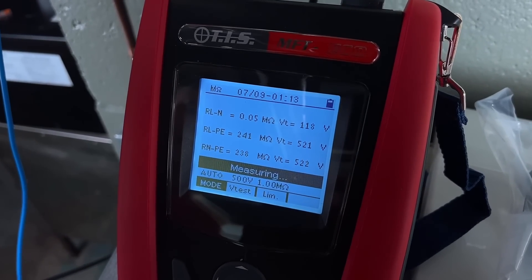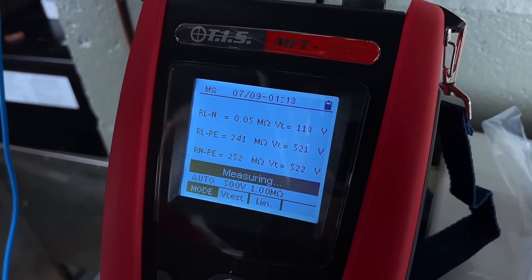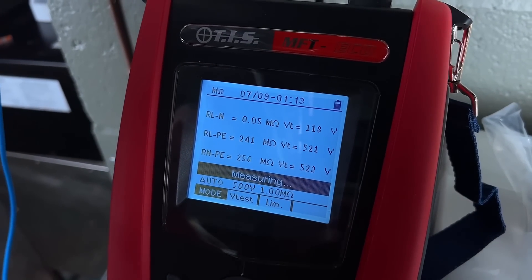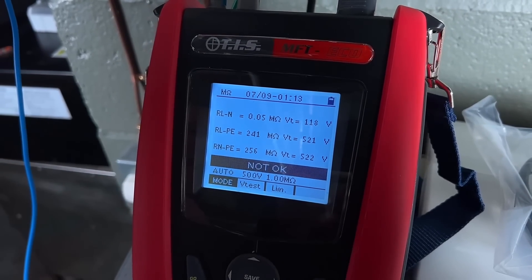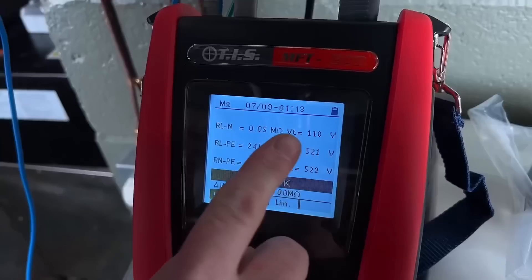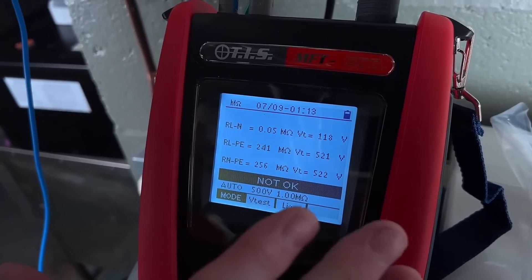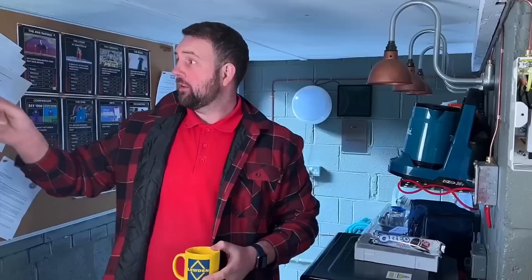It's brought my voltage straight up now to my 500 volt test voltage and it's doing its insulation resistance test, so it's trying to achieve a reading in mega ohms. Then it'll drop down and do my neutral and protective earth when it's happy with that one. So now we're on to the final one. It brings up the voltage straight away, so we're happy with the voltage. We're testing the correct voltage and we're looking for the insulation resistance test. We're slightly higher than before, so we've left something in circuit. I'm sure Rick's standing around with a cup of tea in one hand and a biscuit in the other, but he hasn't removed all our loads. But what's really nice is it's actually throttled back that voltage not to damage that equipment. But now we can search out the piece of equipment that's been left in circuit and repeat the test.